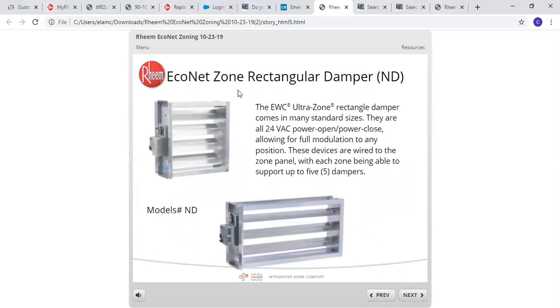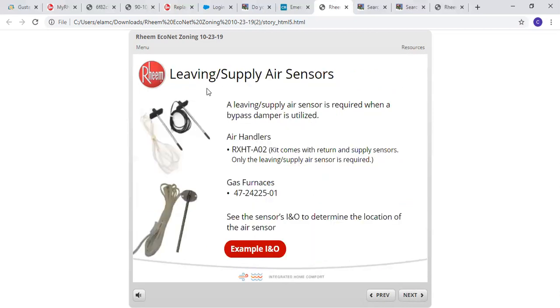This is the Econet rectangular damper, the ND style dampers. They will come in many standard sizes. They are all 24 volt again, power open, power closed. And these are your leaving air supply sensors. A leaving air supply sensor is required when a bypass damper is utilized. We'll get into a little bit when a bypass damper is required. But if you're going to use a bypass damper of some sort, you have to use the leaving supply air sensors.